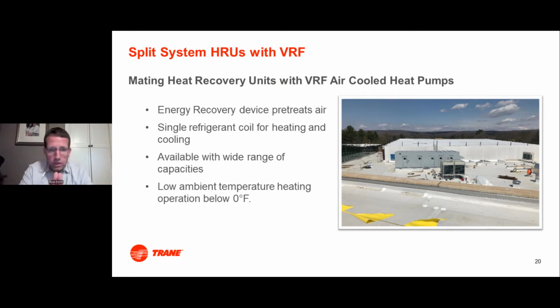This is typically what you'd see with mating a VRF system to an energy recovery unit. In the background, you see a standard AHU energy recovery device inside. In the foreground, you're looking at 4 VRF condensing units. So these condensing units will be tied to the unit through refrigerant piping and have a single heating or cooling coil. Now, this cooling coil can, depending on the size, do all of your outdoor air conditioning in the summertime and in the winter.